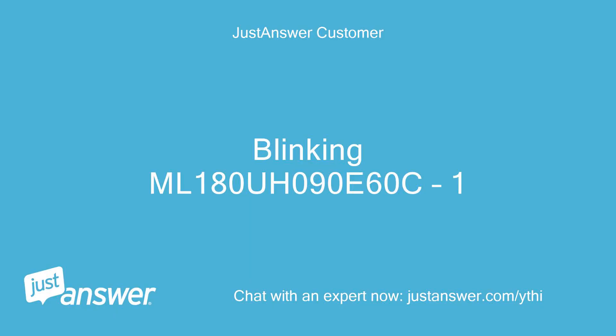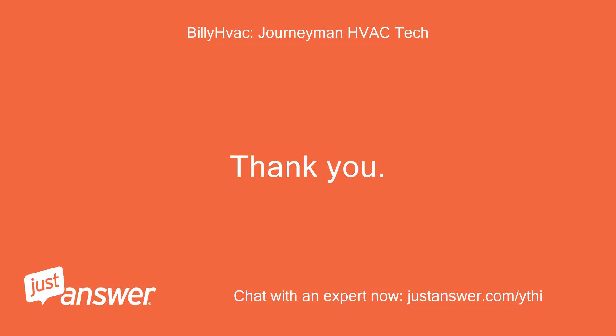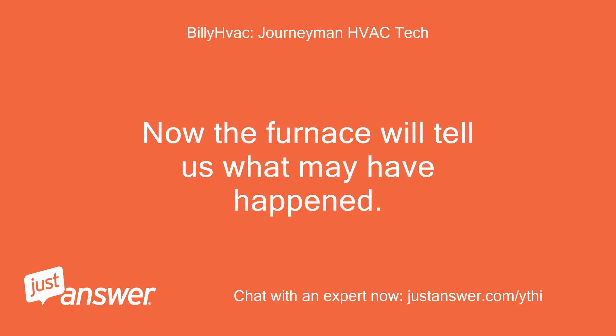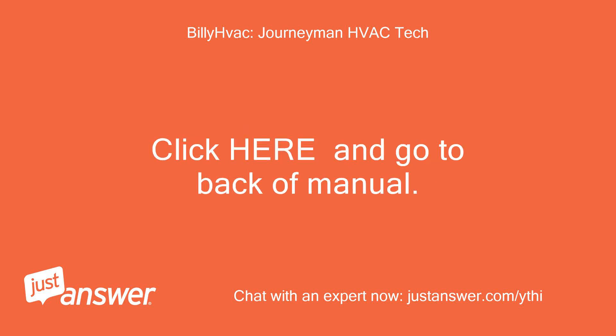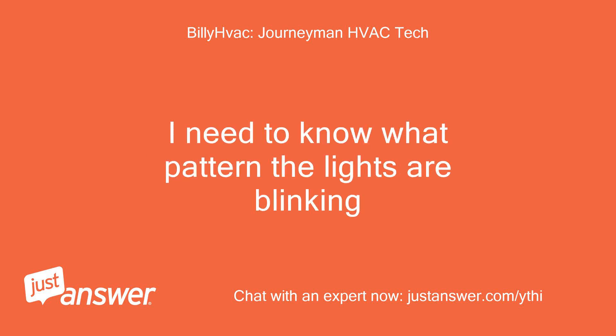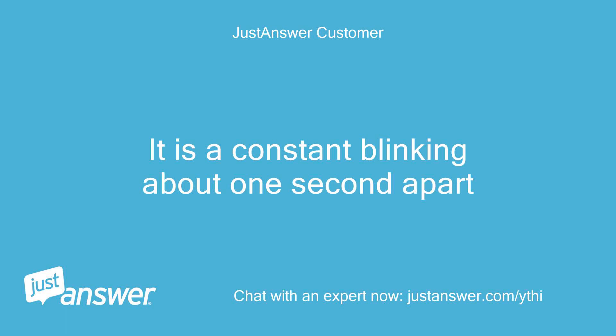Blinking. Furnace model: ML180UH090E60C-1. Now the furnace will tell us what may have happened. Click here and go to the back of the manual. I need to know what pattern the lights are blinking. It is a constant blinking, about one second apart.